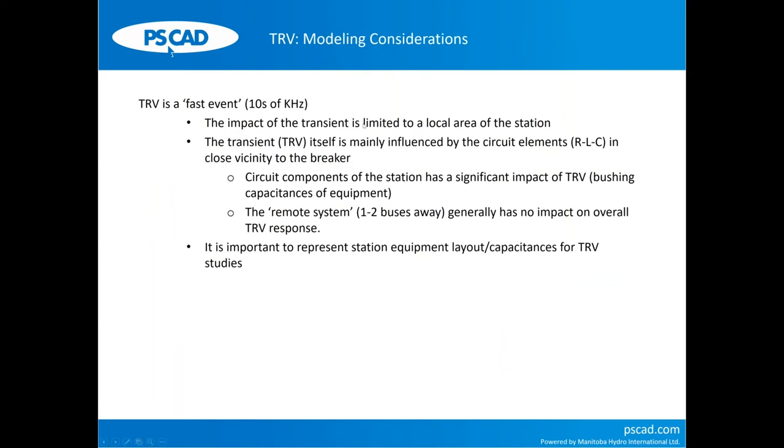So once you come to the modeling considerations, as you know, this is a very fast, very high frequency event. So it's in tens of kilohertz. Therefore, the impact is very localized. So when you're defining the study area, it is normally one or two buses away from the particular station you are studying.